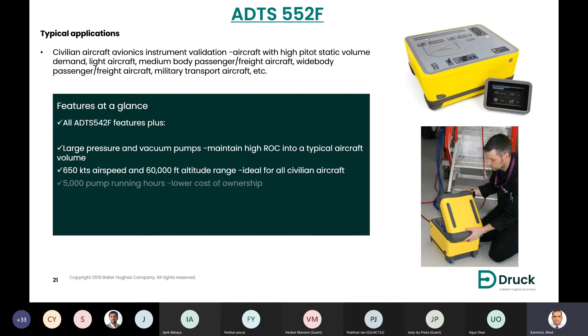It has limitations of 650 knots and 60,000 feet altitude, ideal for all civilian aircrafts, with 5,000 hours of pump capacity. So if pitot-static testing takes 2 hours, you can use the device for 2,500 tests before the pump needs servicing—this gives a really low cost of ownership.